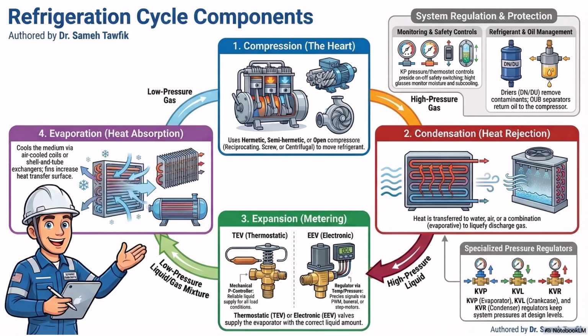And finally, we have the KVR and the NRD, which work together to protect the high pressure side. The condenser side. Right. The KVR is the condenser pressure regulator. If our ship sails into the freezing Arctic Ocean, the outside air is so intensely cold that the condenser might actually overperform. It strips the heat away too fast. Yes. The pressure could drop so low that the liquid refrigerant no longer has the physical force to push its way through the expansion valve at the other end. Oh, the flow just stops. Exactly. So the KVR restricts the flow to artificially keep the pressure high enough to keep the cycle moving, even in sub-zero blizzards. It's genuinely mind-blowing when you zoom out.